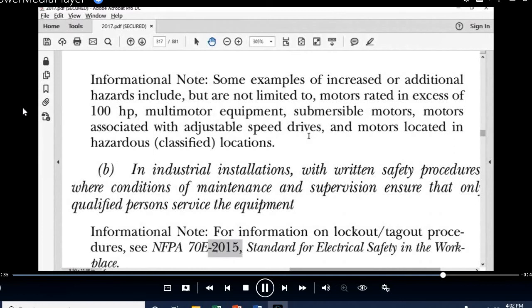Brian, I think this exception is to the where rule. Would this piece of equipment be something you really can't have within sight of the motor? Where would that be located? That'd be a problem. There are a lot of applications. No, but I'm saying where in the circuit would this be the problem? Is it on the supply side of the variable speed drive, or between the drive and the motor? It's between the drive and the motor, right? I just want to get people to understand. I'm sorry, I misunderstood you.